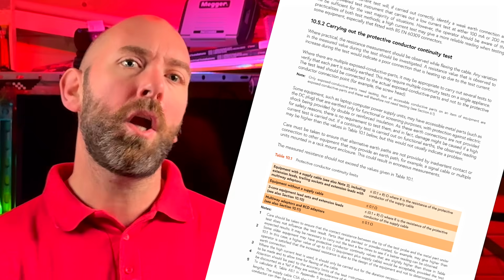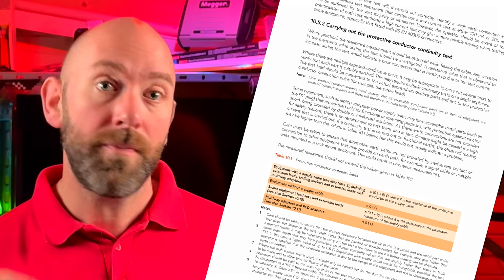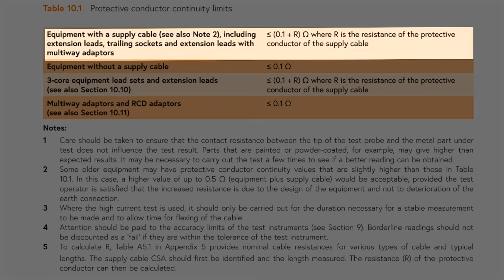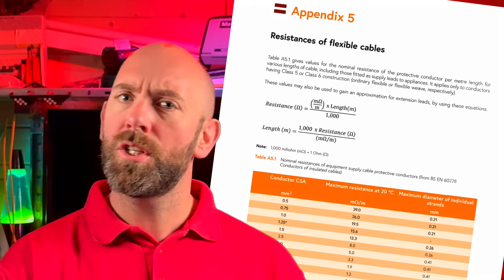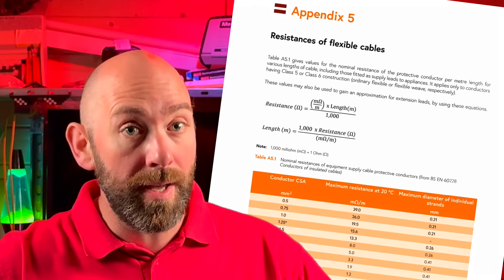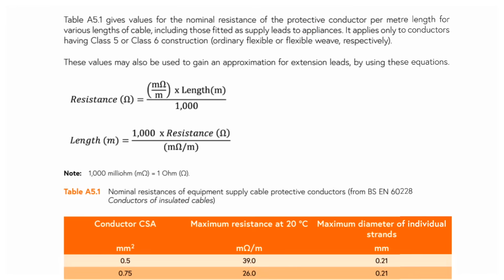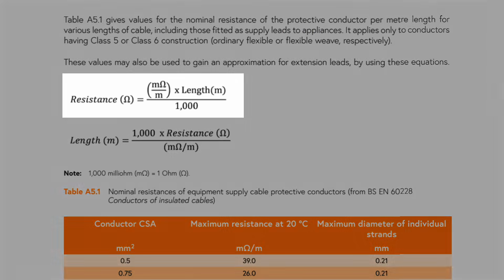Table 10.1 of the Code of Practice gives us the continuity limits for protective conductors. For our extension lead, this is the top row and has a limit of less than or equal to 0.1 ohms plus R. But what is R? R is the expected calculated resistance of the cable. To work that out, we need to dive to Appendix 5, resistance of flexible cables. We are given a couple of formulas here, but the one we're going to use is the one that gives us resistance.